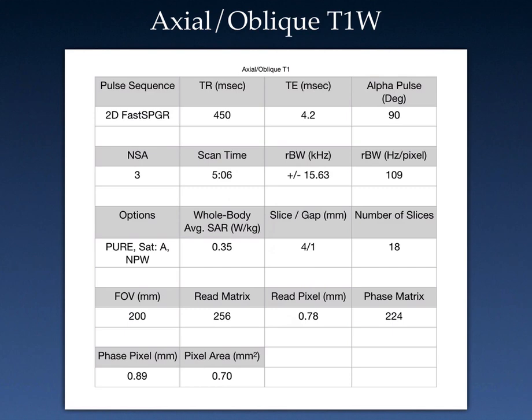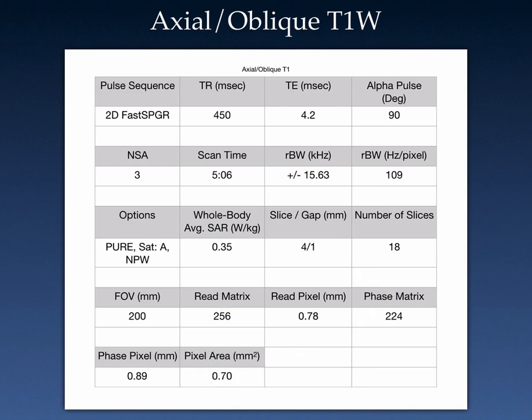For the T1 weighted axial oblique sequence, we went back to the 2D spoiled gradient echo: TR of 450, TE of 4.2 milliseconds, 90 degree flip angle. Three signal averages gave a scan time of 5 minutes and 6 seconds, and the whole body average SAR was 0.35 watts per kilogram. Very good spatial resolution: 4 millimeter slice thickness, 1 mm gap, 18 slices. Field of view 200 millimeters with 256 read, 224 phase, giving a pixel area of 0.7 millimeters squared.